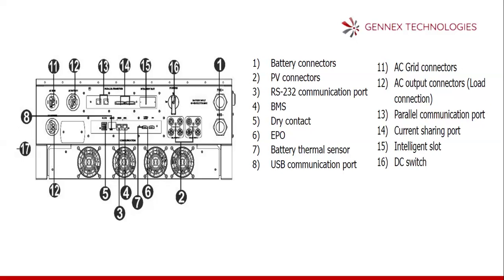As well, there is AC grid. We have only a single AC grid, which is 3-phase. Then we have the AC output connector, which is 2 outputs. It is also 3-phase. The dual phase, they are both 3-phase. The inverter is actually 3-phase all through. 3-phase in, 3-phase out for the 2 outputs. Then there are parallel communication ports, the current sharing ports, and the intelligence slot, which we have discussed that you can use with your SNMP card or with your Modbus card. Then we have the DC switch. This one controls the PV input. You use it to turn on the PV or turn off the PV.